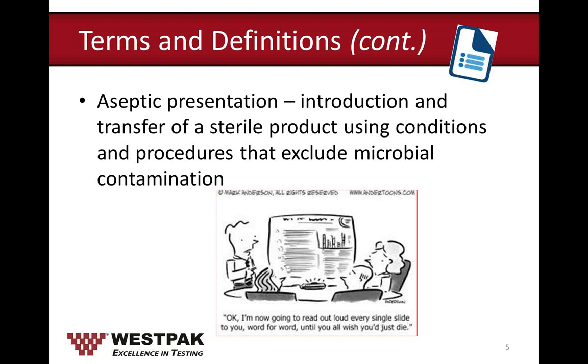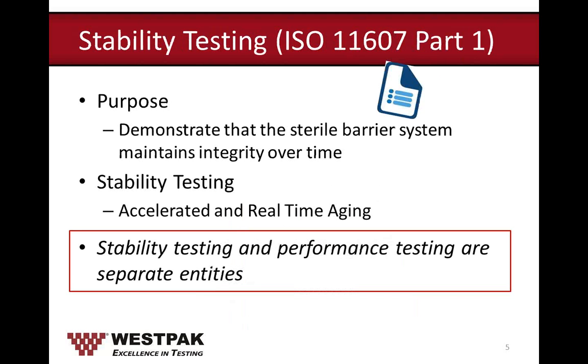Another term is aseptic presentation — the introduction and transfer of a sterile product using conditions and procedures that exclude microbial contamination. The purpose of stability testing is to demonstrate that the SBS maintains integrity over time, according to ISO 11607 Part 1.